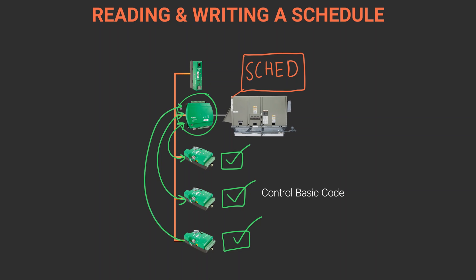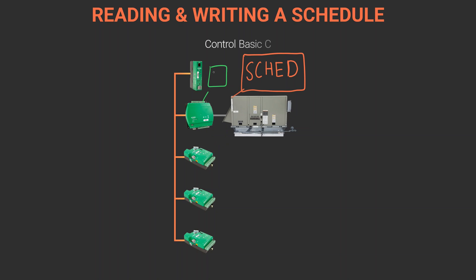Let's look at a schedule example. An air handler controller has the schedule and needs to notify downstream VAV controllers that are dependent on its air supply. We can move that data in two different ways. Using writes, you may choose to add ControlBasic code to the air handler unit that will push the data to the VAV controllers.